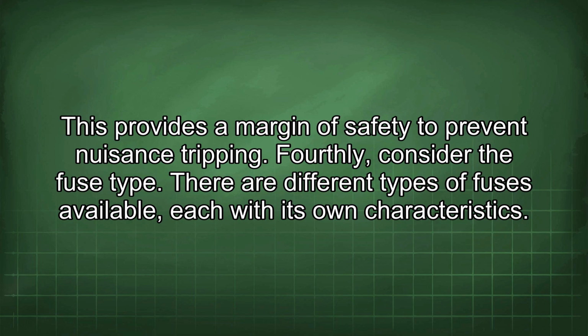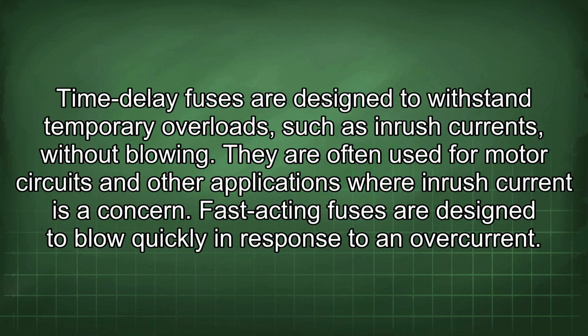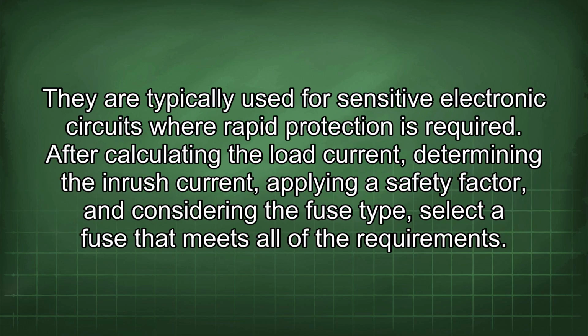Fourthly, consider the fuse type. There are different types of fuses available, each with its own characteristics. Time delay fuses are designed to withstand temporary overloads, such as inrush currents, without blowing. They are often used for motor circuits and other applications where inrush current is a concern. Fast-acting fuses are designed to blow quickly in response to an overcurrent. They are typically used for sensitive electronic circuits where rapid protection is required.